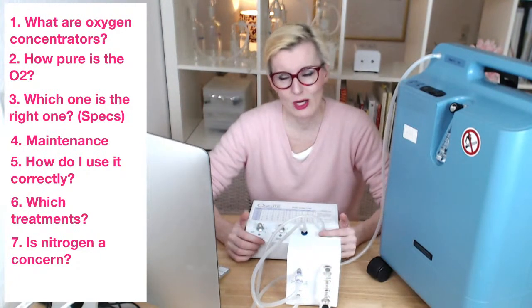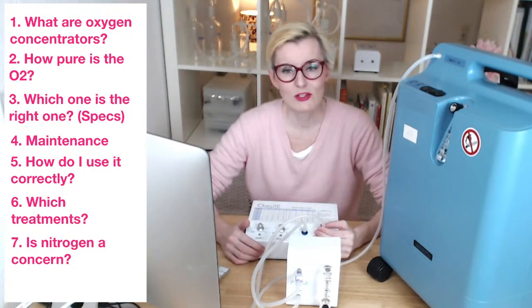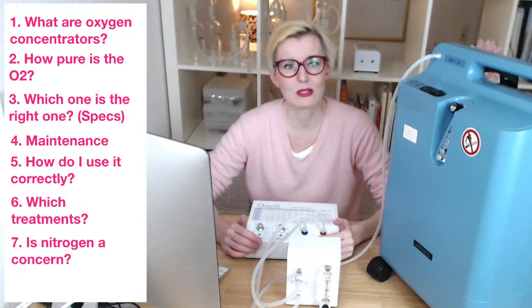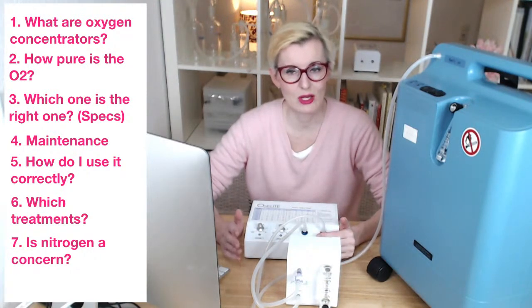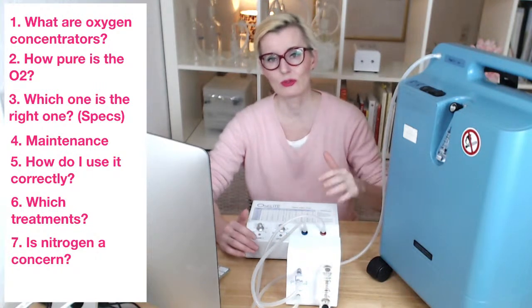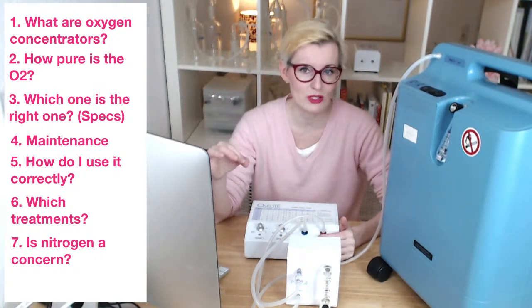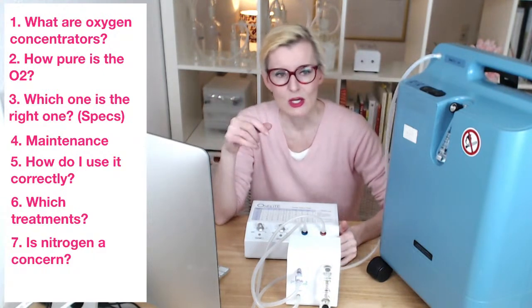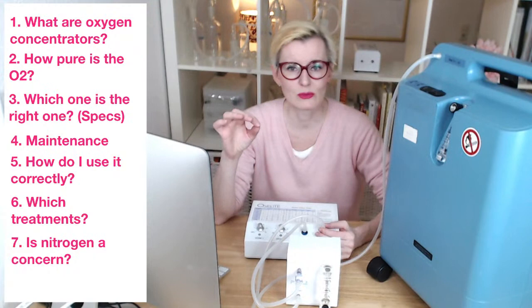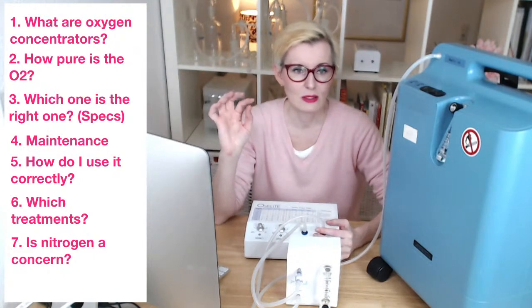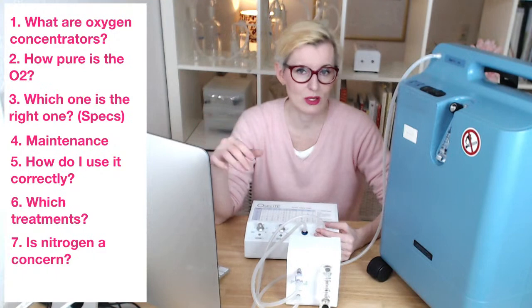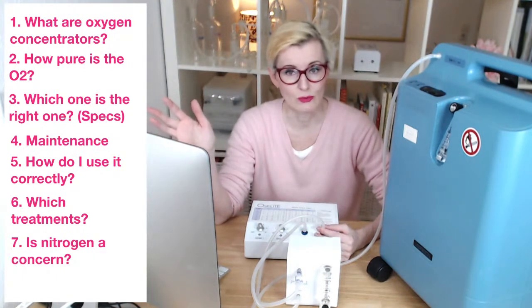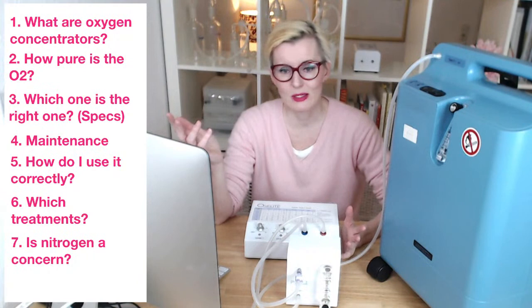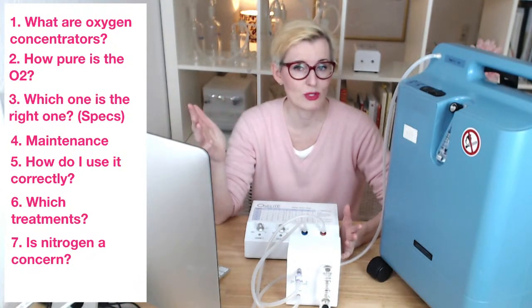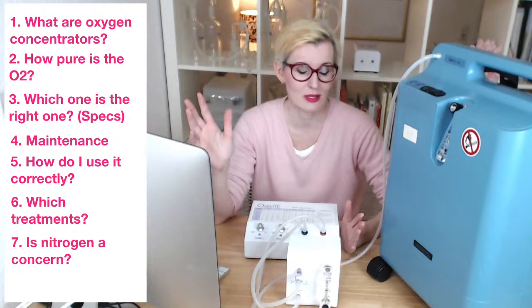Another manufacturer, I believe it was Invacare or Respironics, I'm not sure, said that what comes out of the machine is between 95 and 97% oxygen. It also depends on the flow: the lower the flow, the higher the oxygen purity. So it can be between 95 and 97% oxygen, and then up to 5% nitrogen, and some argon and some CO2. According to my information, it can be anything between 0 and 5% nitrogen. This is the maximum, they said.